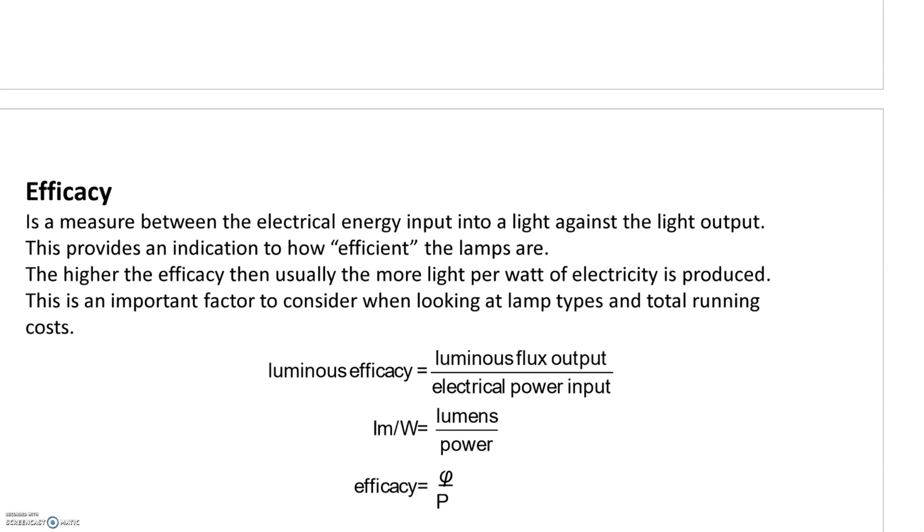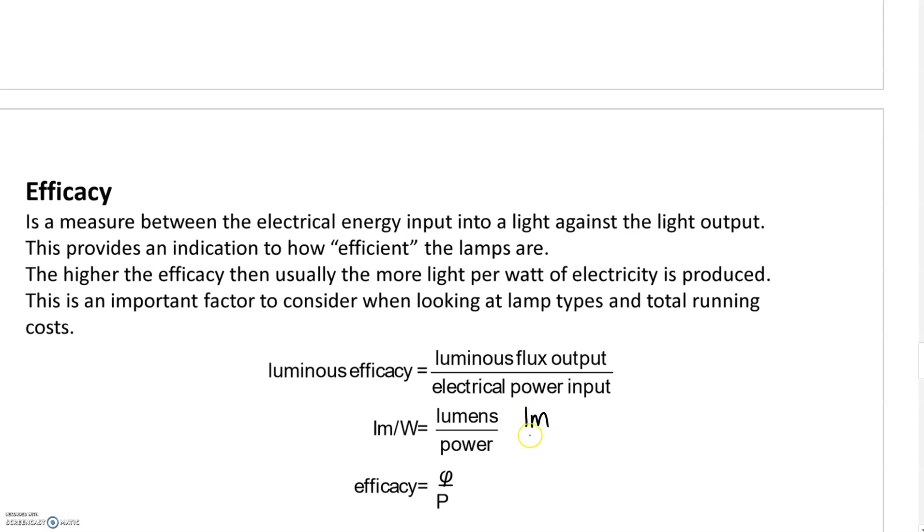We have luminous flux output, which is the amount of light emitted measured in lumens, and electrical power input measured in watts. When we divide lumens by power, that gives us a number known as efficacy, measured in lumens per watt.